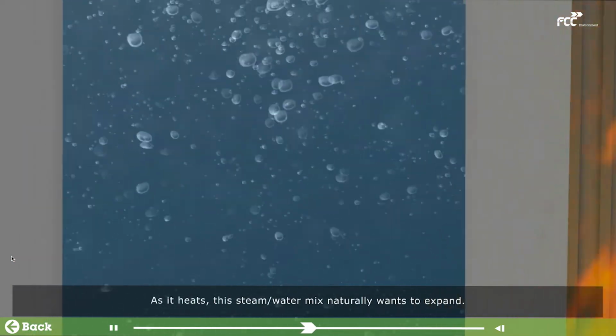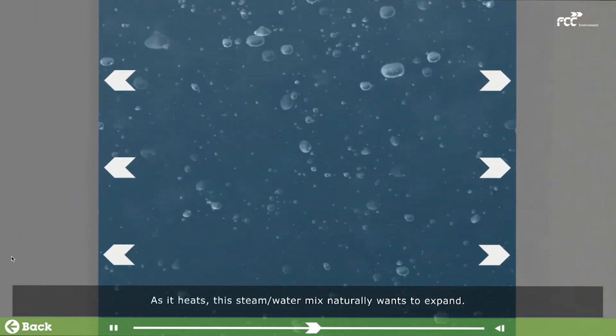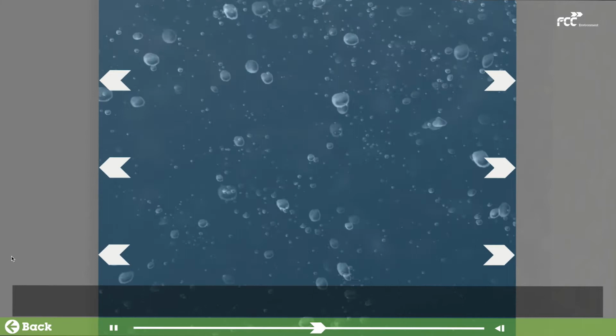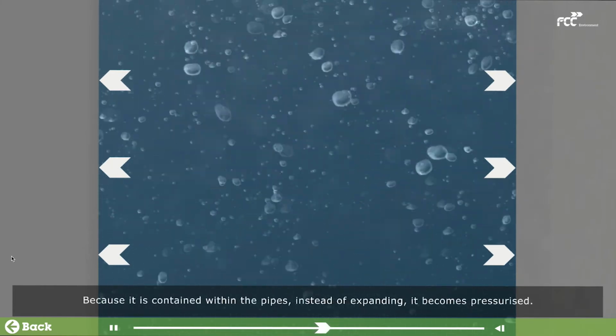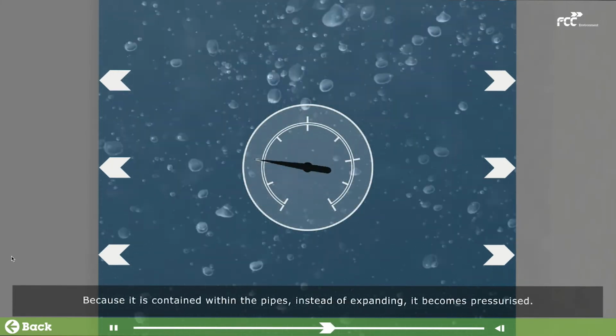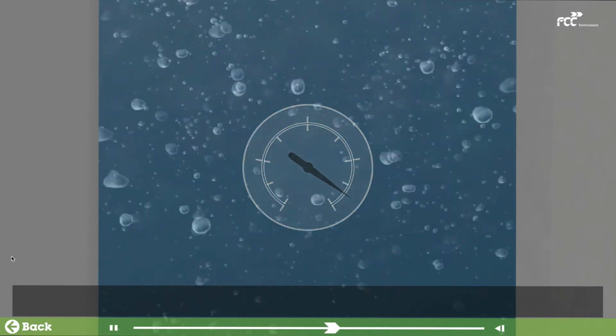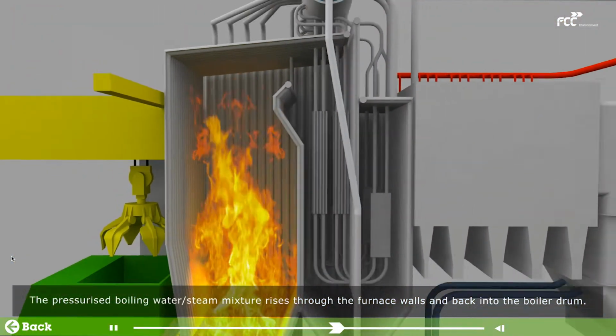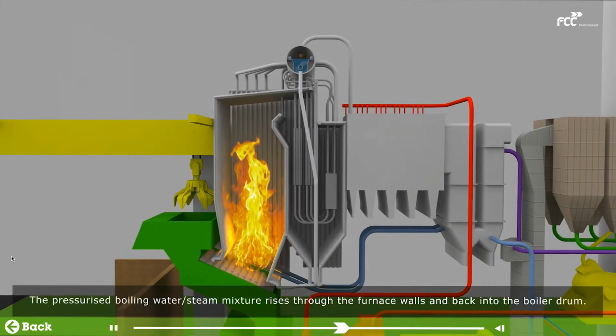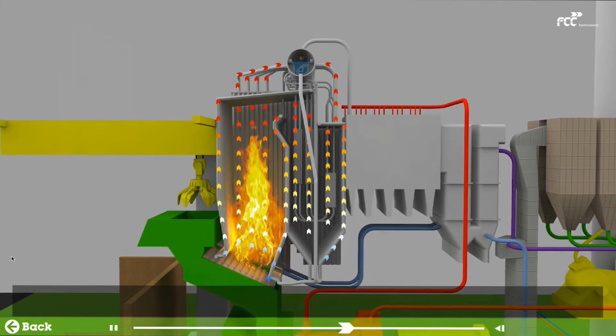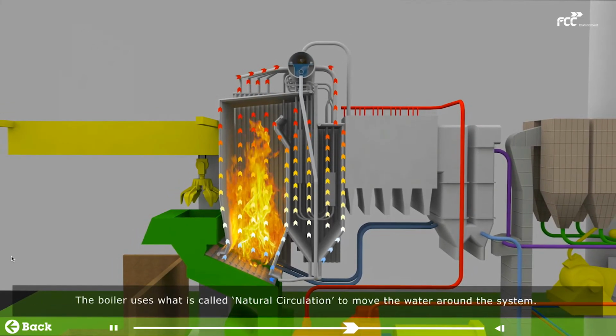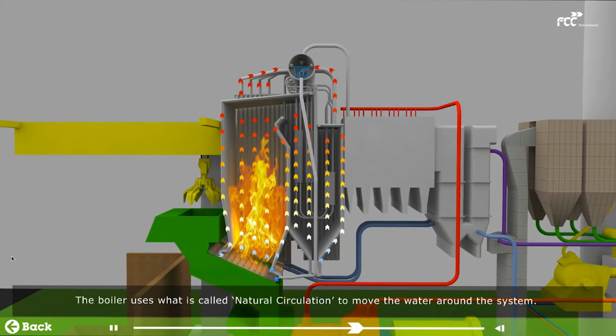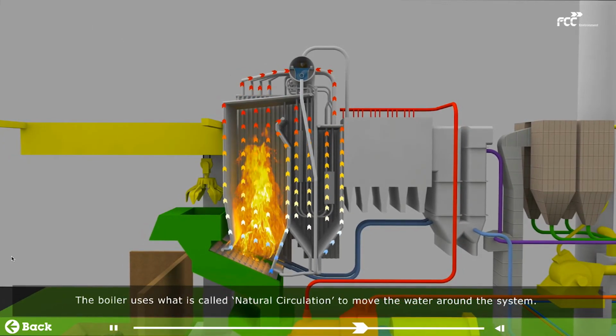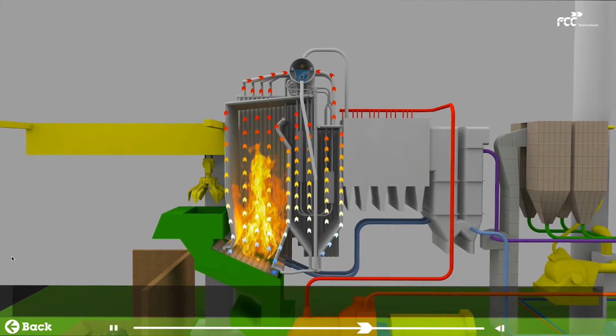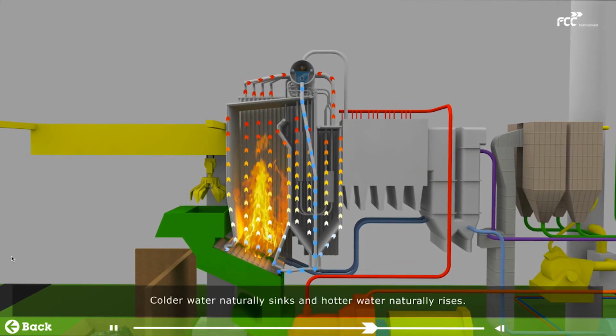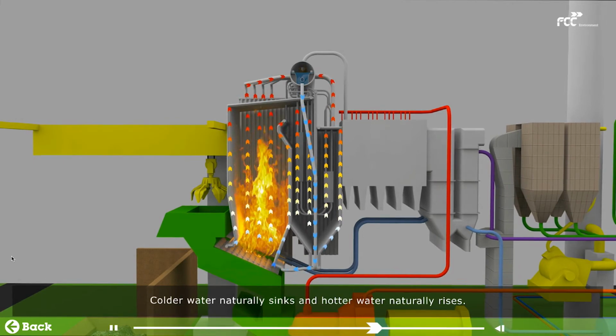As it heats, this steam-water mix naturally wants to expand. Because it is contained within the pipes, instead of expanding, it becomes pressurized. The pressurized boiling water-steam mixture rises through the furnace walls and back into the boiler drum. The boiler uses what is called natural circulation to move the water around the system. Colder water naturally sinks, and hotter water naturally rises.